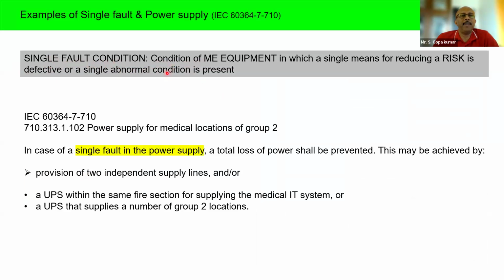Single fault condition means a condition of medical electrical equipment in which a single means for reducing a risk is defective. Please note, it's very important. A single means of reducing a risk: there is a chance of a risk, and there is a means to reduce the risk, and that means is defective. That means there is a fault, or a single abnormal condition is present.